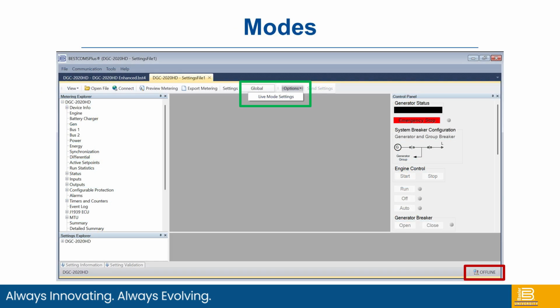So once you connect a PC and the BestComs Plus software to a DGC-2020HD, you can use it for programming the HD, but you can also go live. What's nice is when you're trying to troubleshoot or commission. I expanded the upper left-hand side here, but you can see that in live mode, there is a bunch of different screens that will actually come up, and they're configurable. So you can look at circuit breakers, temperatures, pressures, basically everything that the DGC is monitoring or controlling. You can bring up multiple screens in live mode at the same time to be able to monitor what's going on.